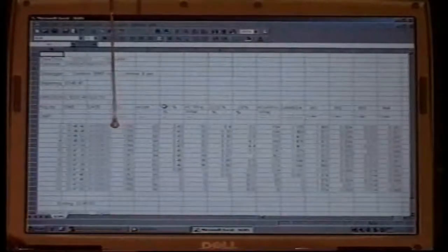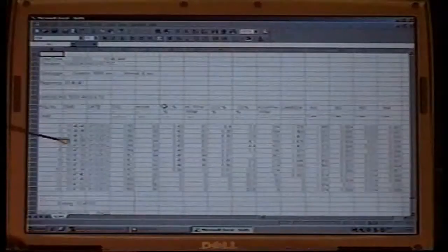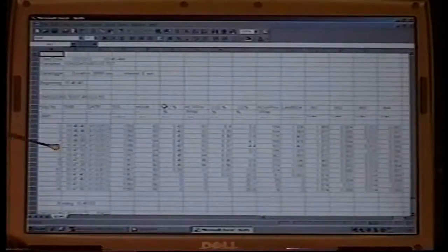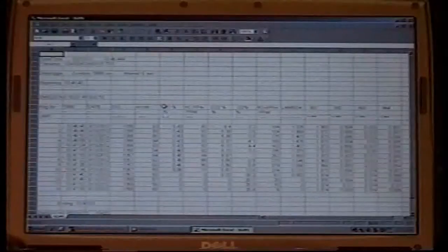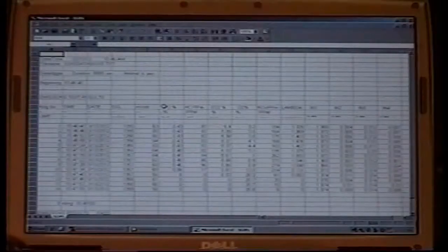As you can see, we have the gases that we measured. There's the information from the pulse counter. Also, on each gas entry on Excel, you have a time and a date stamp, and this applies to all the data that's on here. This is the data from the expansion port, the battery voltage. Anyway, that pretty well covers the gas data information. Let's go back into the actual program, and we'll take a look at the calibration menu.